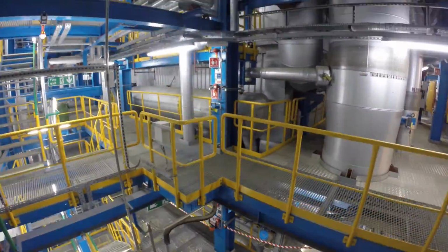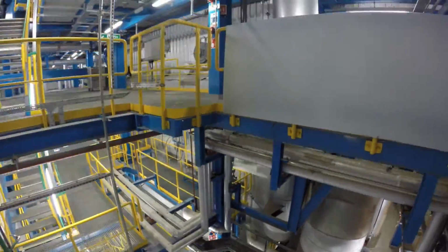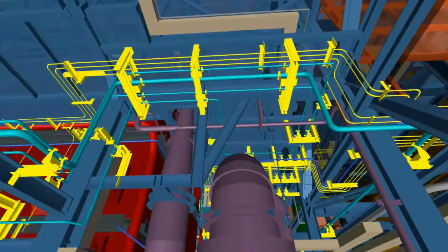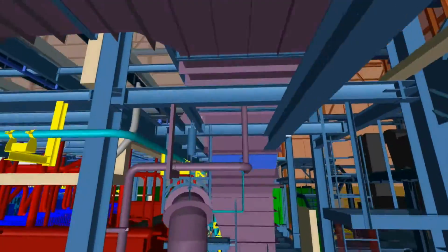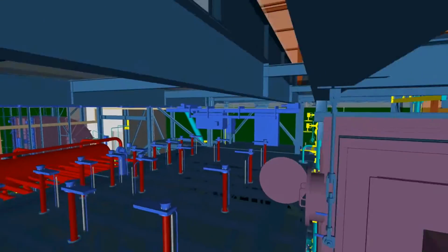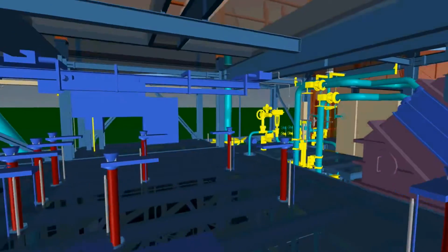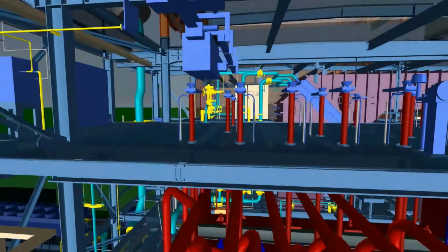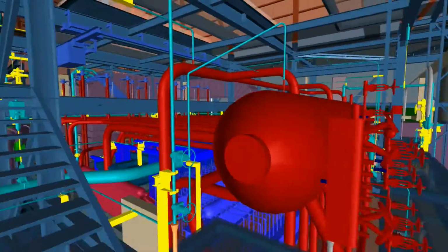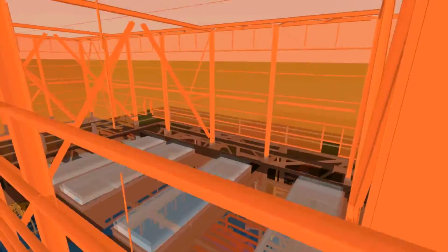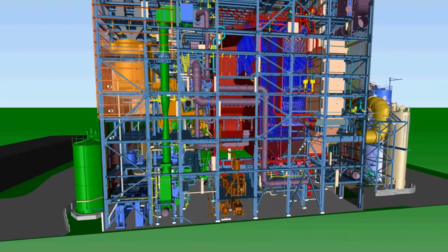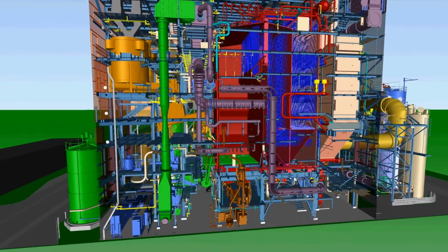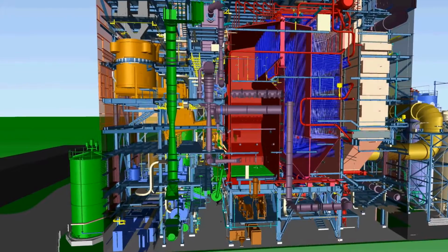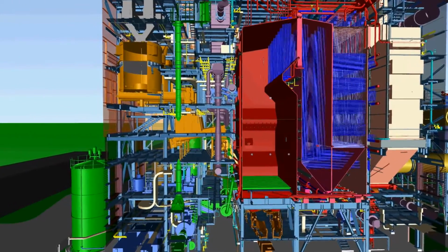The boiler has a guaranteed efficiency of 91.9% at the design point. This results in a gross electrical output at the turbine generator of 33 megawatts at design conditions. The boiler design is tailor-made for a fuel with higher corrosion tendency, like recycled wood, with its higher heavy metal and chlorine content. The arrangement of the heating surfaces is carefully selected so that the corrosion risk is minimized, which is confirmed by similar applications.